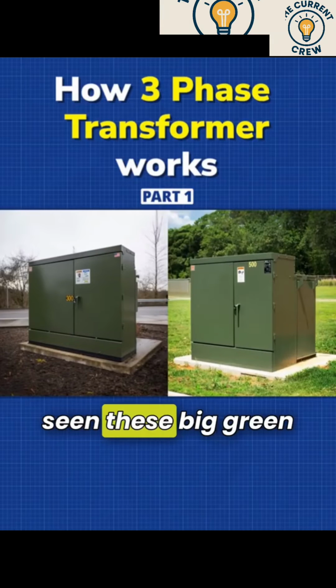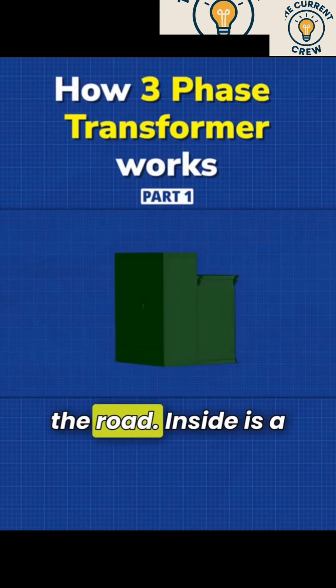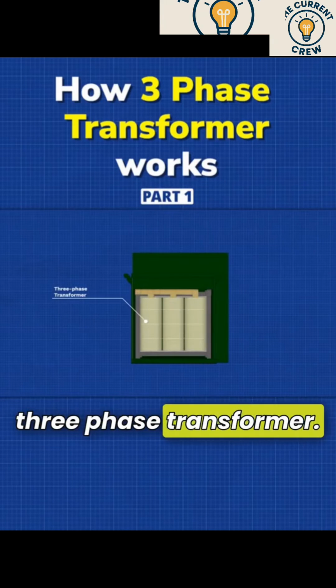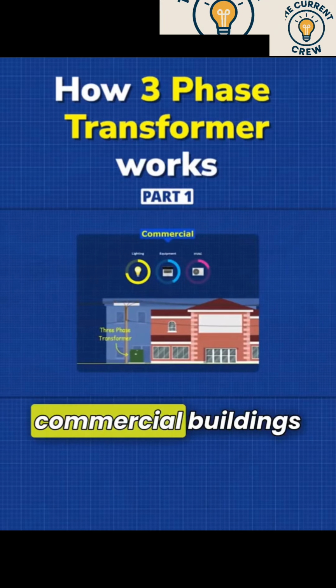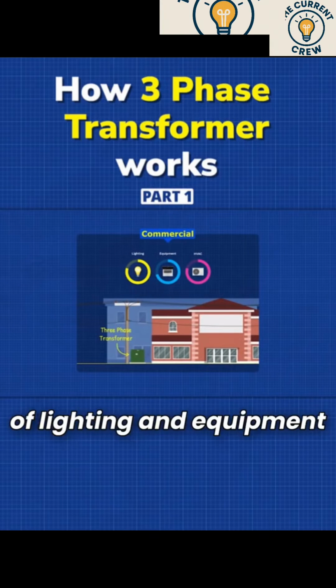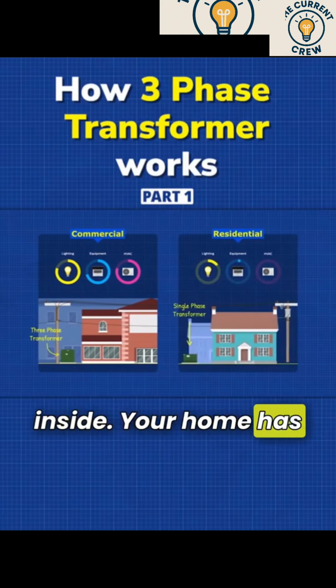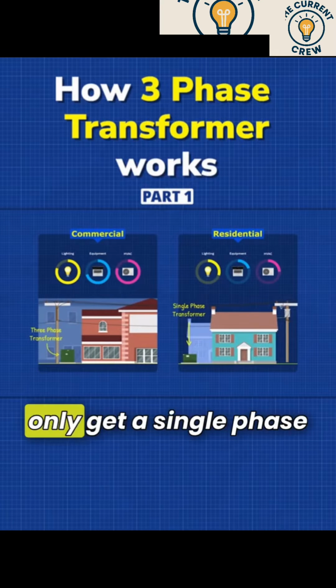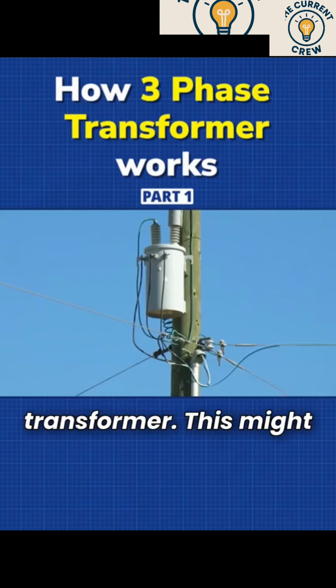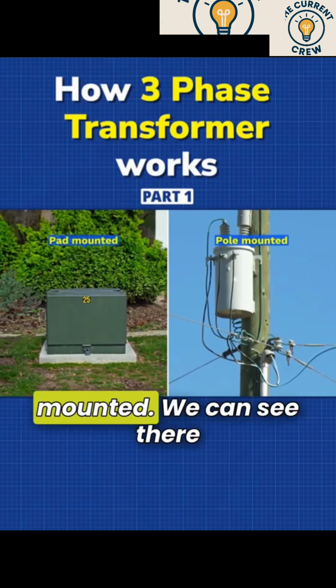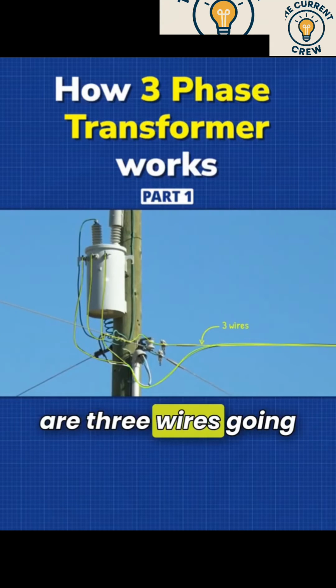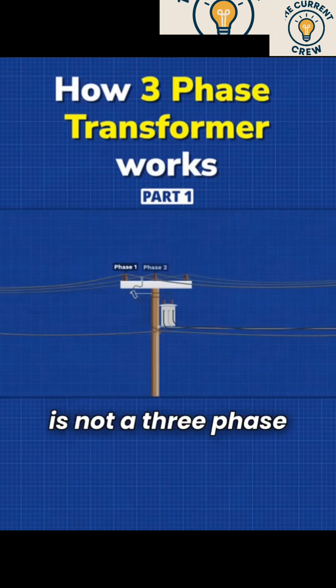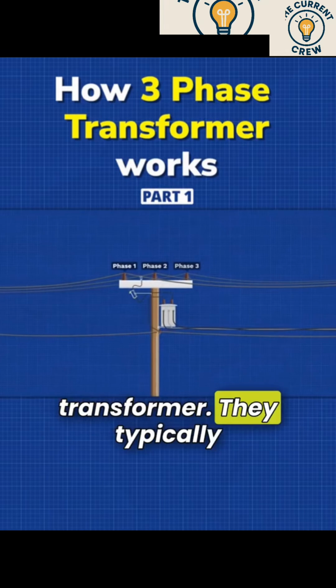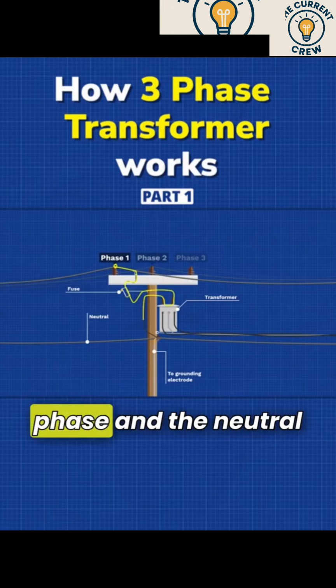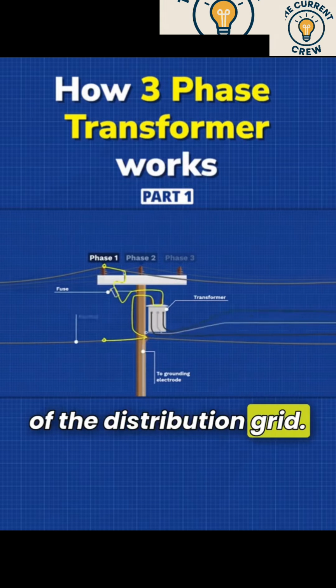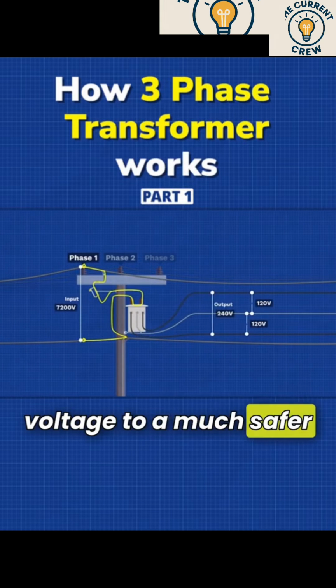You've likely seen these big green boxes at the side of the road. Inside is a three-phase transformer. These supply power to commercial buildings because they have a lot of lighting and equipment inside. Your home has much less stuff, so you only get a single-phase transformer. This might be pole-mounted or pad-mounted. We can see there are 3 wires going to the home, but this is not a three-phase transformer. They typically connect to just a single phase and the neutral of the distribution grid. It then reduces this voltage to a much safer level.